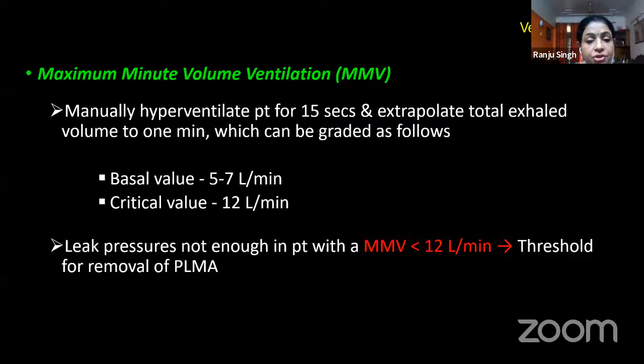be kept in mind. The leak pressures are not enough in a patient who has an MMV of less than 12 liters per minute. And this is the threshold which has been cited for removal of the PLMA. So always do this maximum minute ventilation test in every patient after insertion of the supraglottic devices.